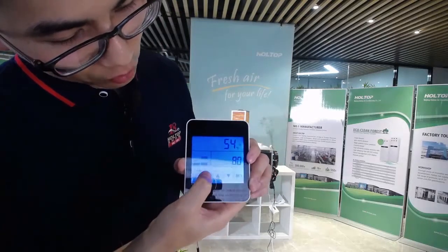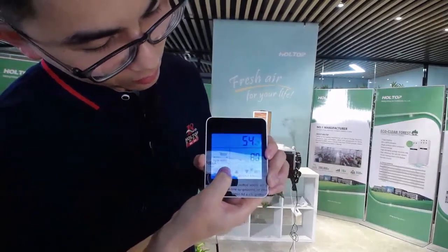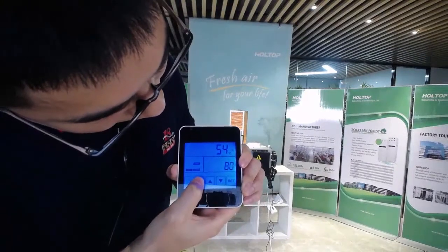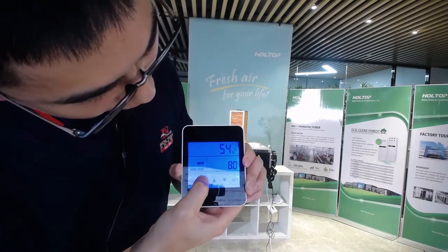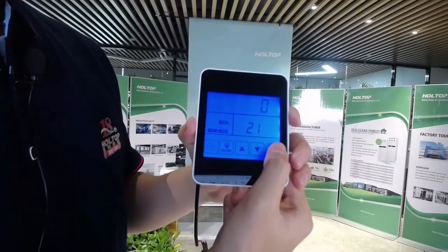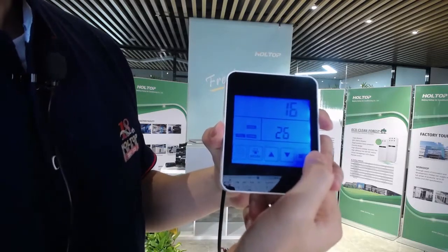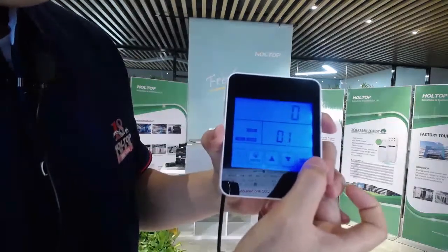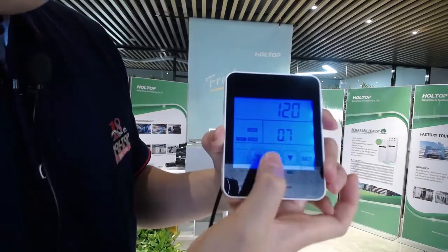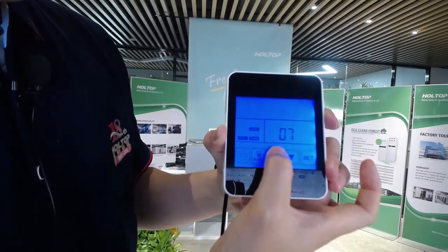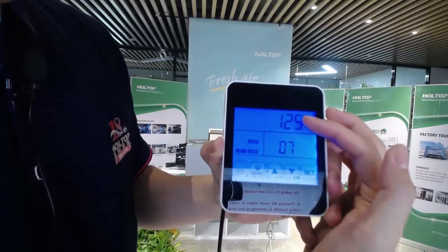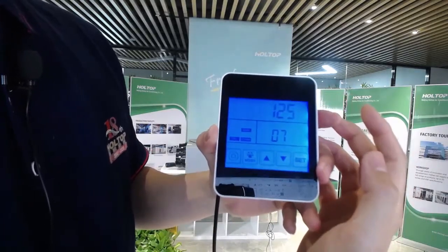Yes, complicated. You first press the mode button for 6 seconds, so we enter a different mode. One moment. Okay. For the carbon dioxide setting, you press the mode button for 6 seconds. You will enter this new interface where you can select parameters from one. We will go to parameter 07. Then you can press the mode button to enter the parameter setting and change this value. 125 means 1,250 ppm for the concentration. And the range is from 80 to 250, right? Meaning 800 ppm to 2,500 ppm.